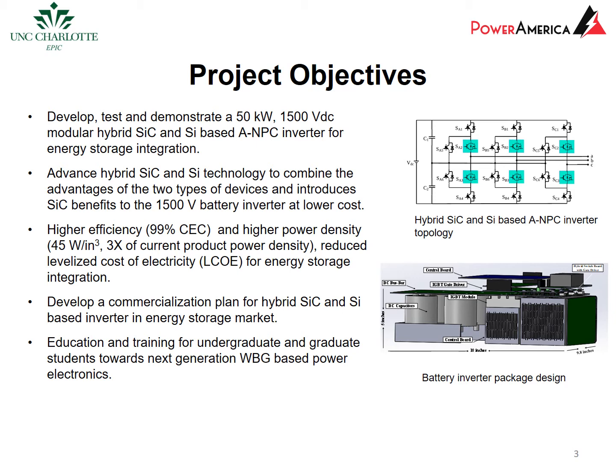This proposed solution is an active neutral point clamped (A-NPC) inverter based on an optimized unipolar device in parallel with a bipolar device. Our approach combines the advantages of the two types of devices and introduces silicon carbide benefits to the 1500 volt battery inverter at a significantly lower cost compared to state-of-the-art pure silicon carbide inverter technology.